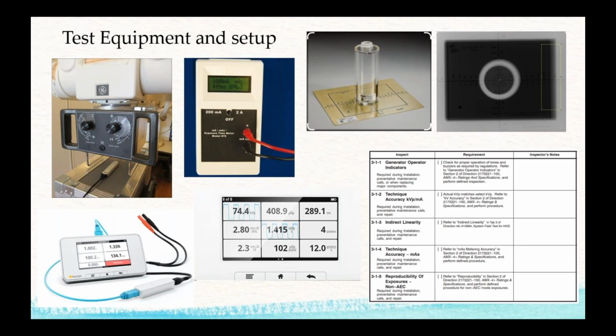I'm going to check my waveform for flatness, and I'm also going to check to make sure that it's within about 2% plus or minus 1 kV, and go up through the scale, 60, 70, 80, all the way up to 120 kV, making those shots at different mAs.